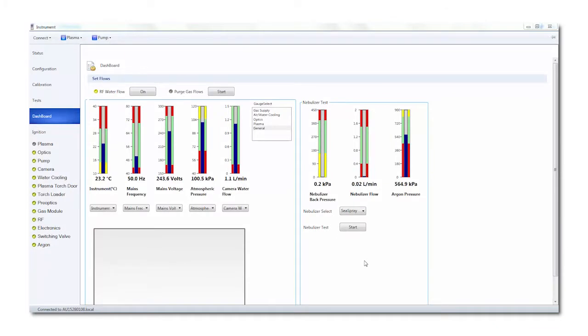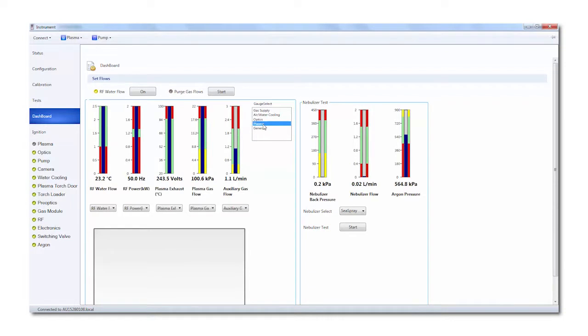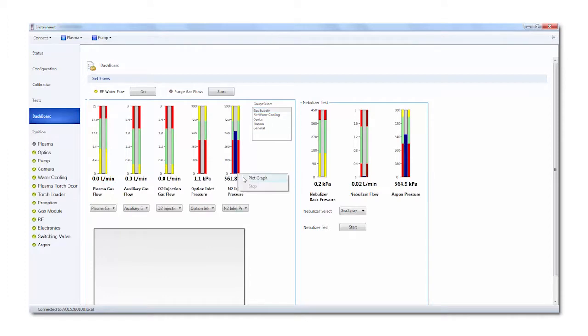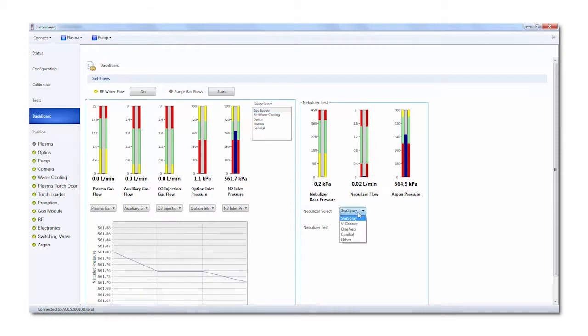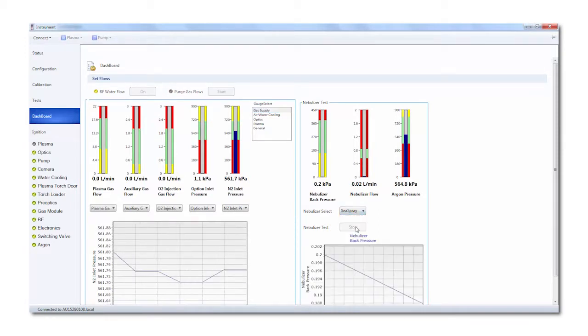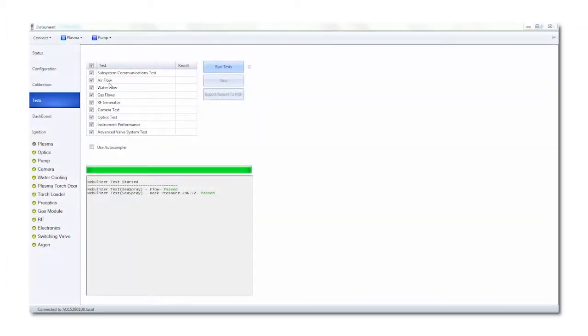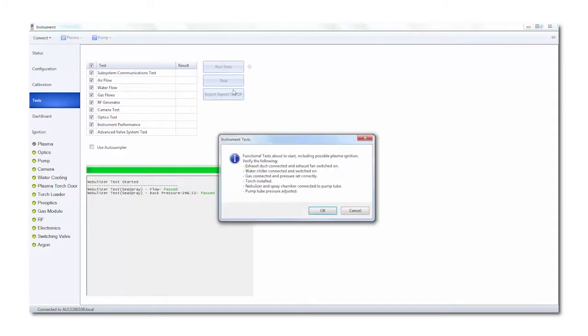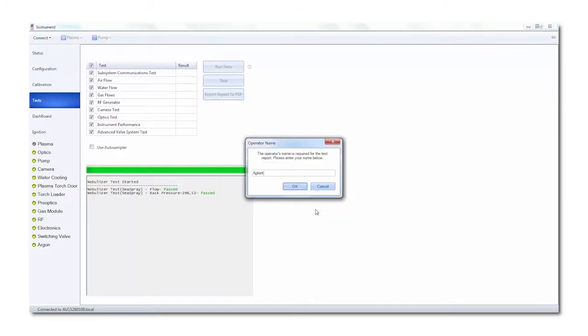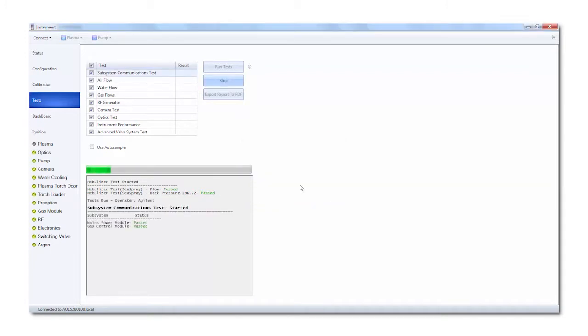Now, the operator can narrow down to a specific module if they do get a fail to help identify where a fault may exist. Access to the instrument dashboard visually informs the user to the status of the instrument around instrument hardware and utility supplies. There are multiple categories of information that can be displayed through the gauge select. Any of these can be graphed for ongoing monitoring. There is even the ability to perform a nebulizer test. Select the type of nebulizer and start the test. Selection of any or all of the instrument tests is up to the user. As the tests progress, values will be displayed and a pass or fail will indicate the outcome of these tests. The results to this system check can be reported if required.